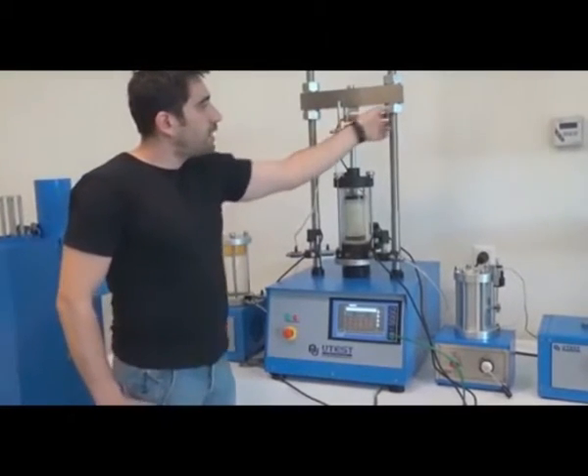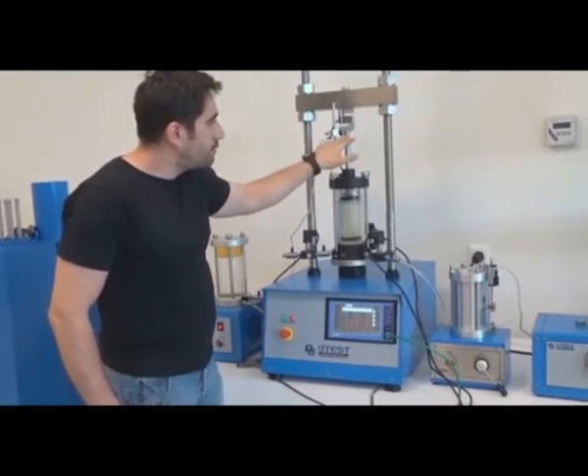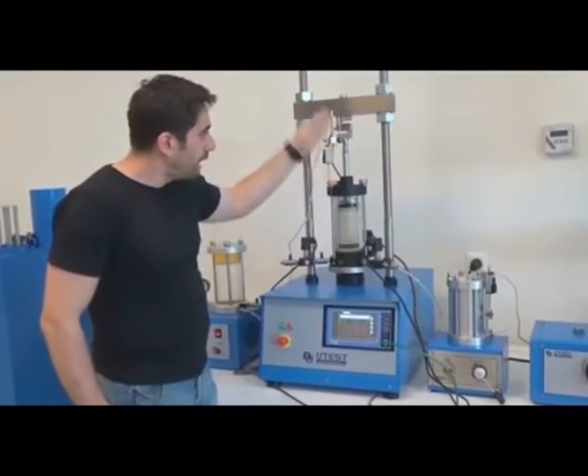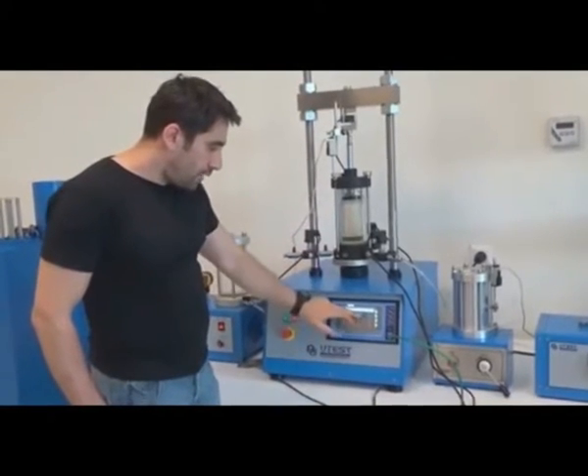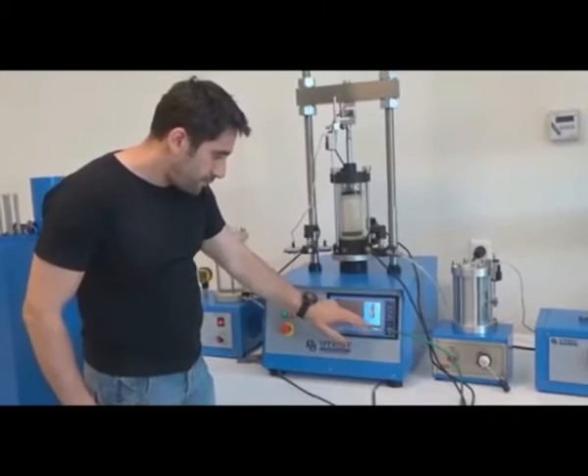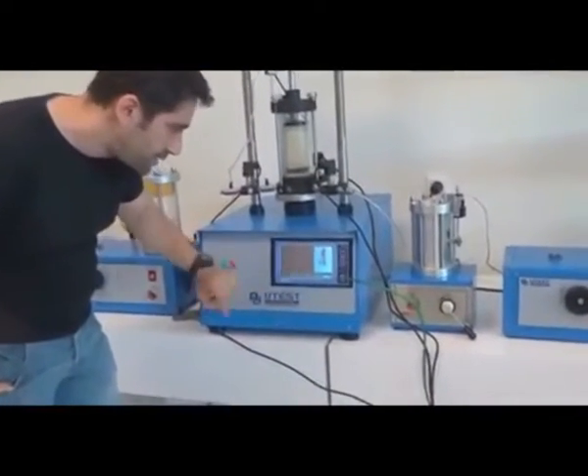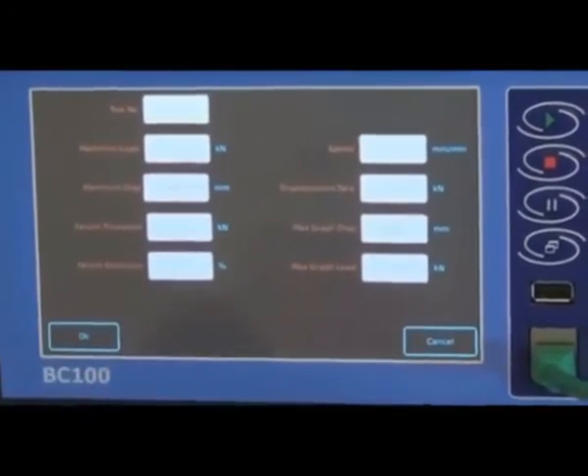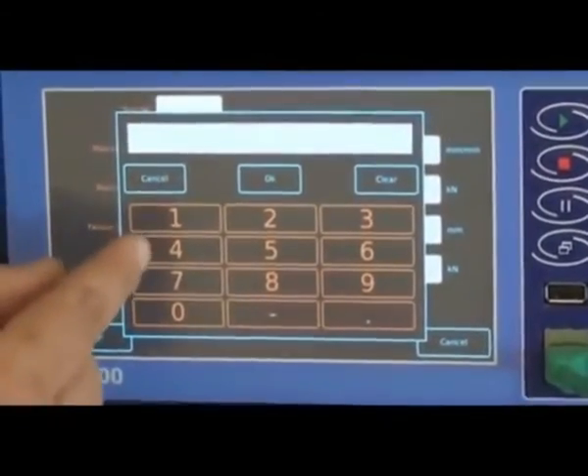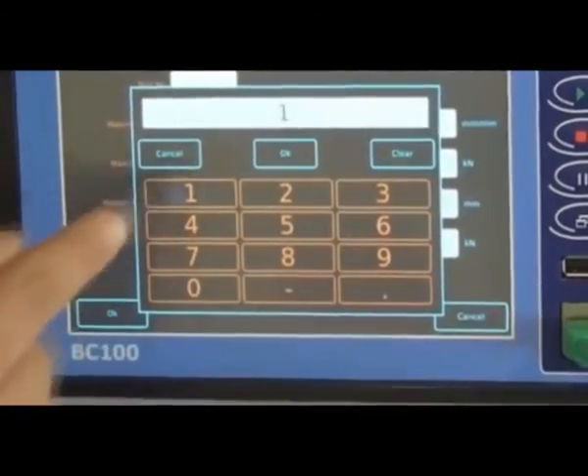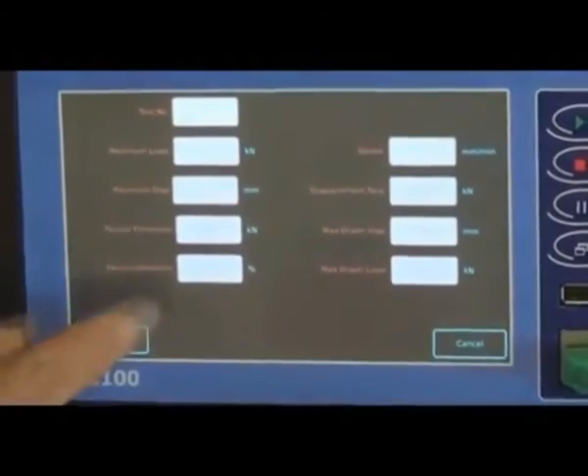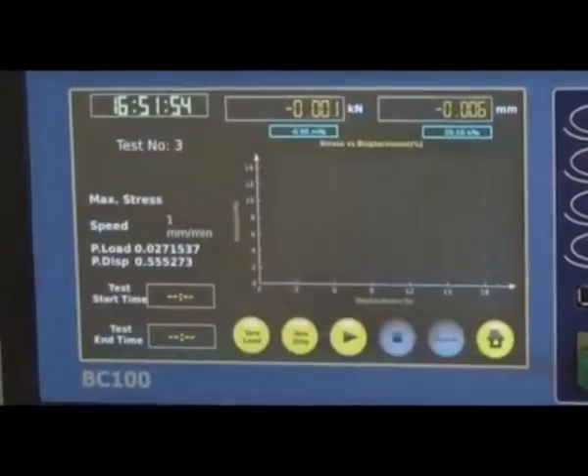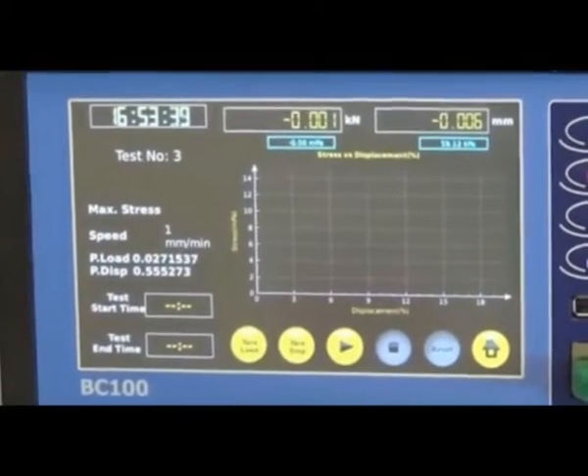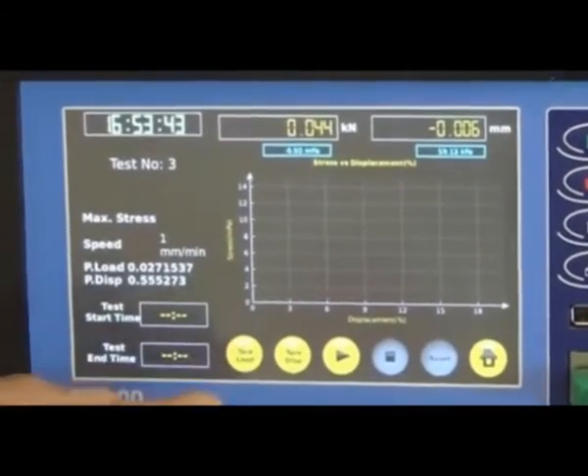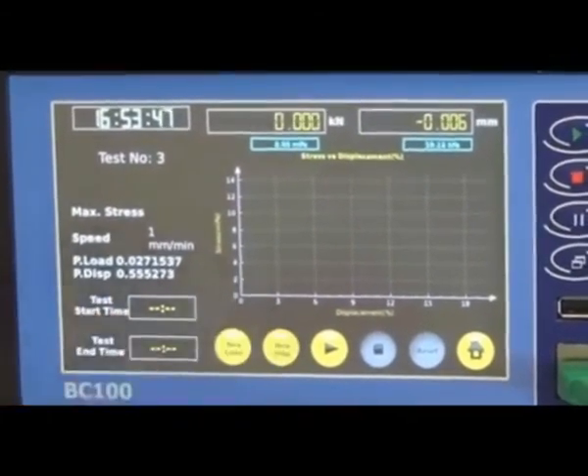We have arranged the screws and cross beams for the load cell and piston just to touch, and they are all centered. Now on the test screen, we are going to choose test parameters, and we are going to choose a predetermined compression speed on the shear stage. Let us choose 1 millimeter per minute. It is okay now. On the test screen, you can see the speed as 1 millimeter per minute. We are going to tare and reset the load to 0 and tare the displacement.